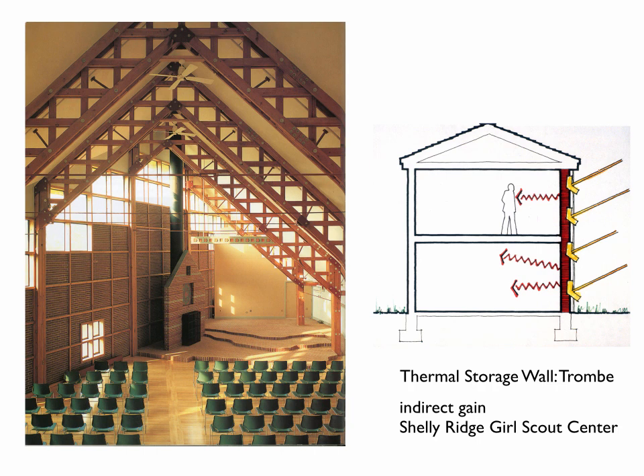The second system is the thermal storage wall. We just saw the Shelly Ridge Girl Scout Center as one example. The glazing has an air space behind it, and the heat is absorbed into the thermal storage medium — in this case, a masonry wall coated with an absorptive surface. At the Shelly Ridge Girl Scout Center there are no vents, so it's a radiant transfer through the mass. You can also insulate in the cavity at night or in summertime.